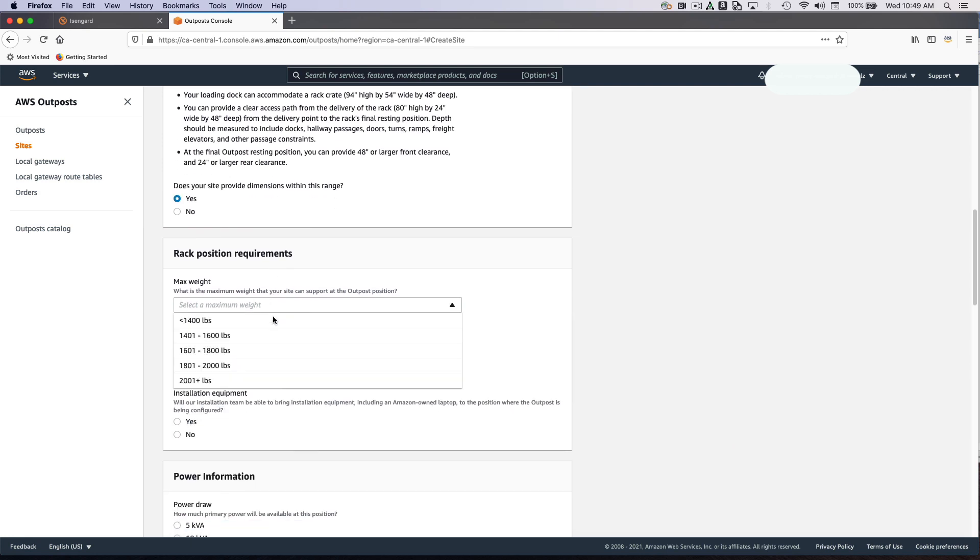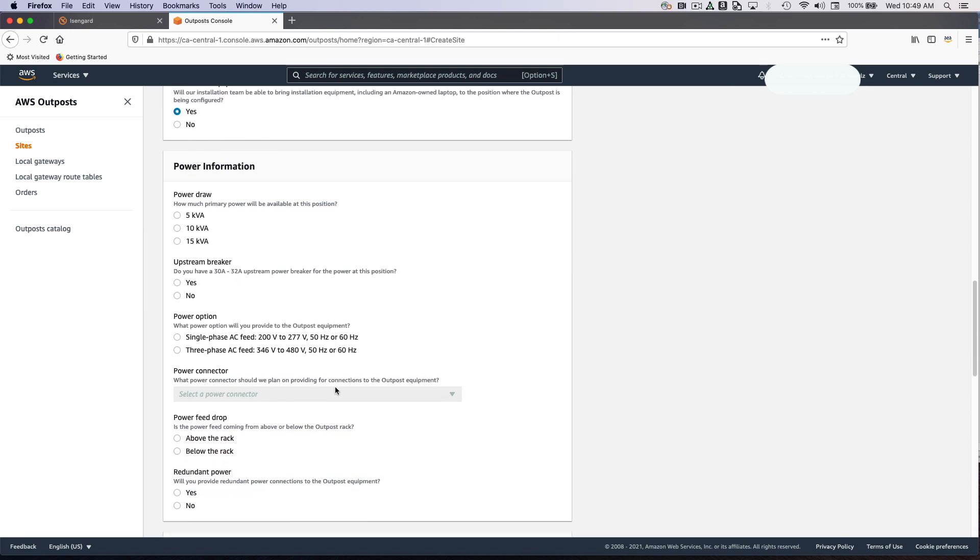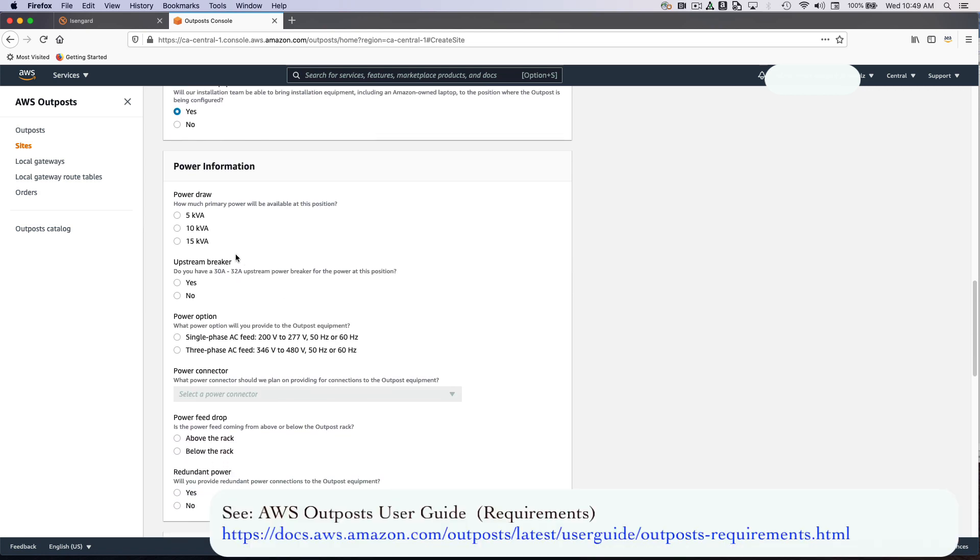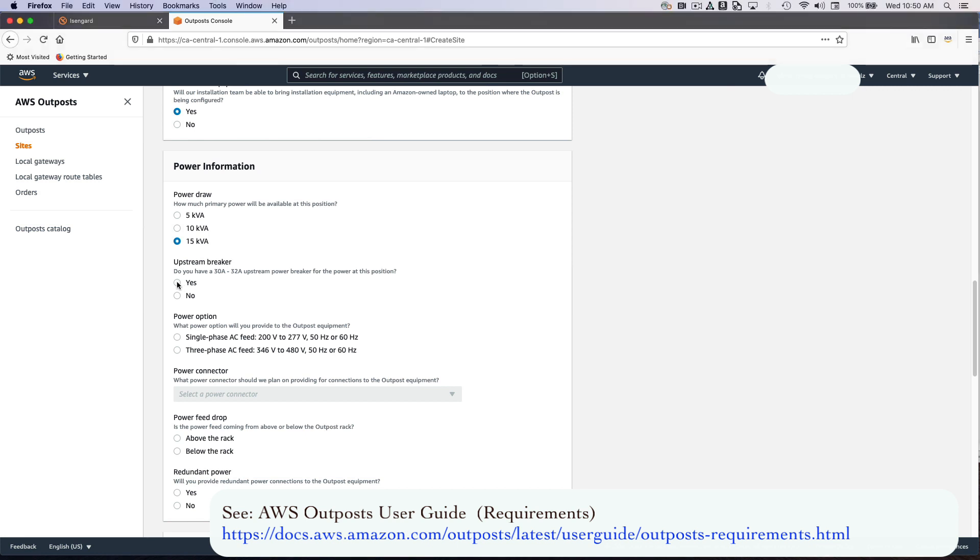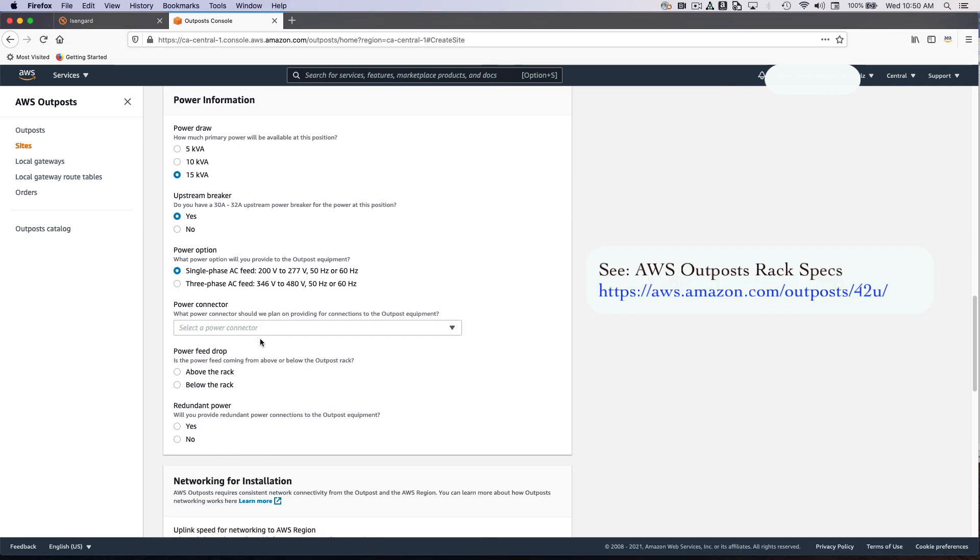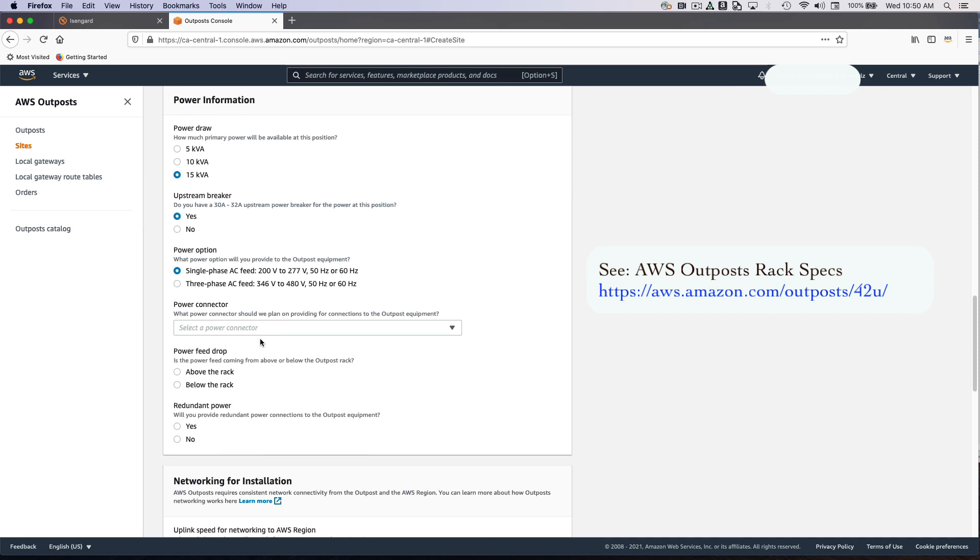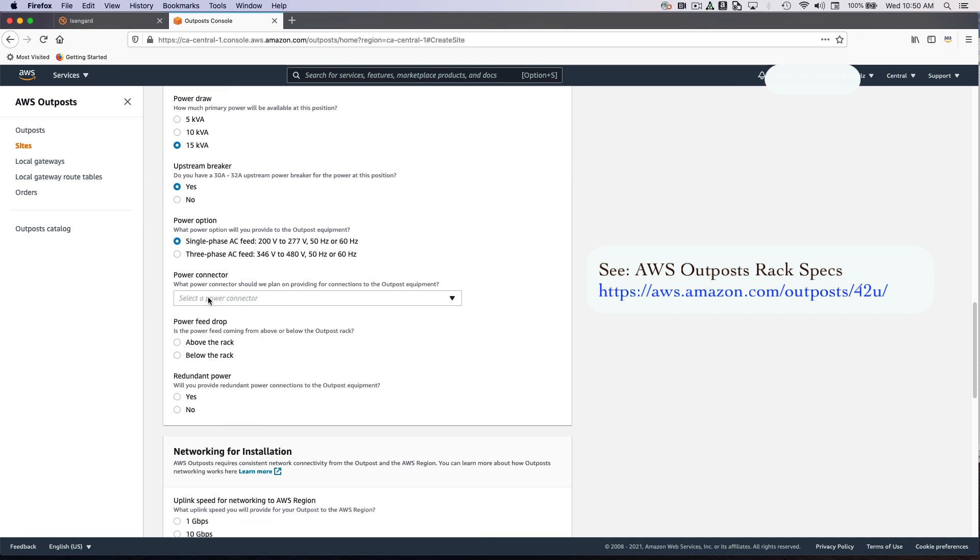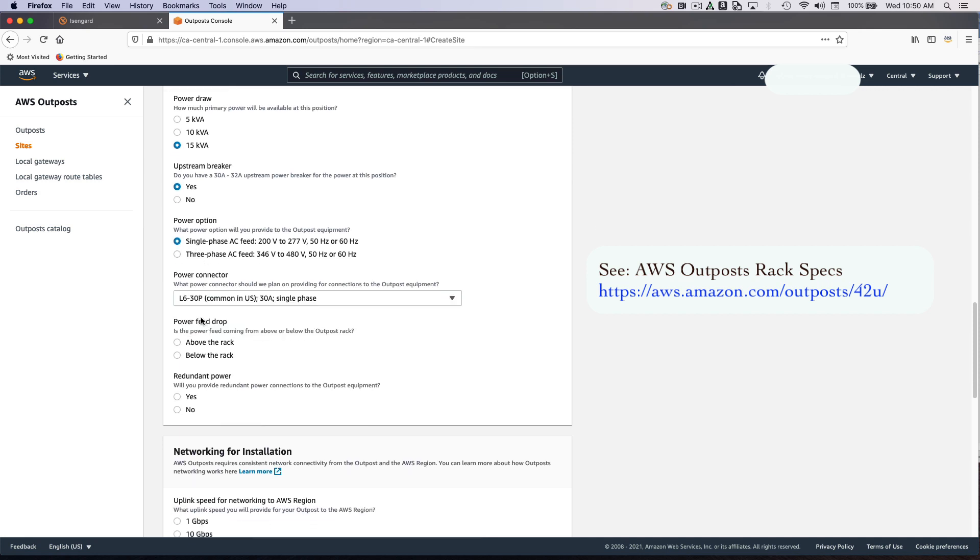The next question deals with certain physical minimums, such as minimum power or maximum weight that you can support. We can provide bracing equipment at no extra charge, and this becomes really important if your location is in a seismically active area. When dealing with power, we want to know how much primary power will be available in this position. I'm going to select a value in the case of this example. You do have an option to inform us whether you prefer single-phase or three-phase power, and depending on these selections, various power connectors will be available to you.